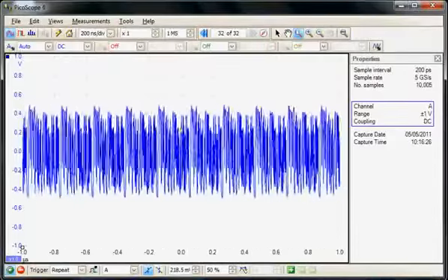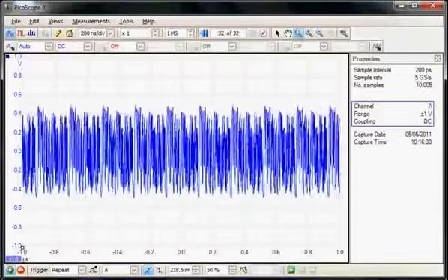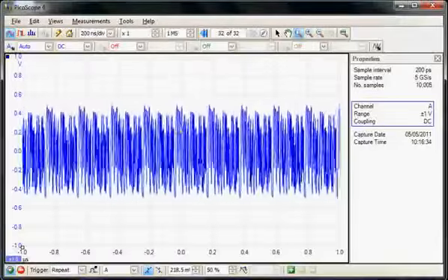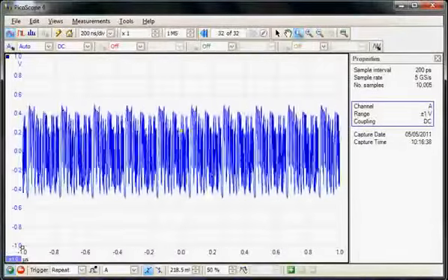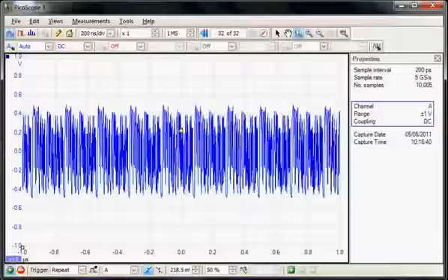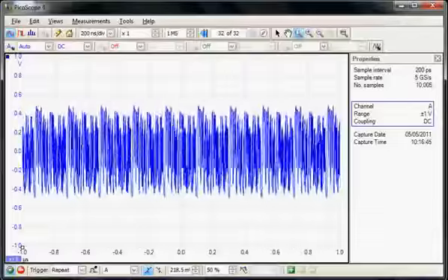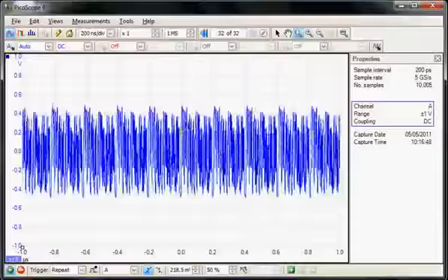The 6000 series has an analog bandwidth of 350 megahertz, so it's possible to monitor signals up to this bandwidth. The particular signal applied at present is in fact an STM4 signal, which has a clock rate of 622 megahertz, so it would not be possible to measure the clock, but the data rate is half of that, 311 megahertz, so we could use this instrument to monitor that data.